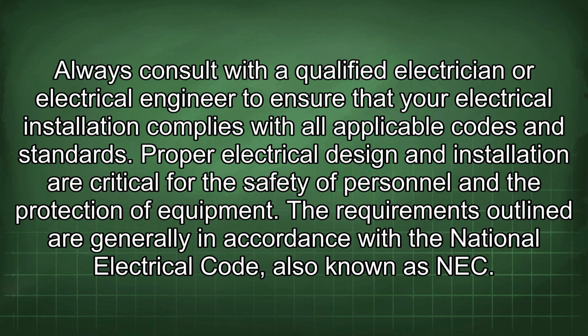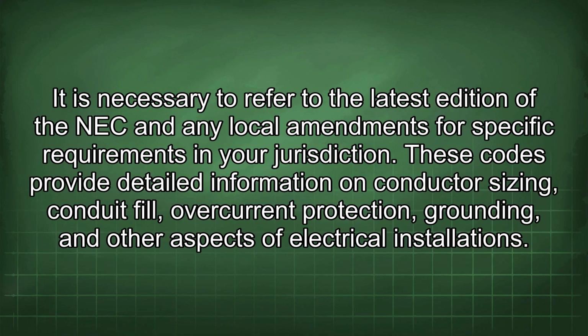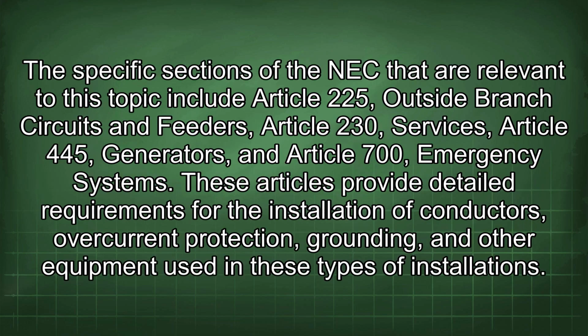Proper electrical design and installation are critical for the safety of personnel and the protection of equipment. The requirements outlined are generally in accordance with the National Electrical Code, also known as NEC. It is necessary to refer to the latest edition of the NEC and any local amendments for specific requirements in your jurisdiction. These codes provide detailed information on conductor sizing, conduit fill, overcurrent protection, grounding, and other aspects of electrical installations. The specific sections of the NEC that are relevant to this topic include Article 225, Outside Branch Circuits and Feeders, Article 230, Services, Article 445, Generators, and Article 700, Emergency Systems.